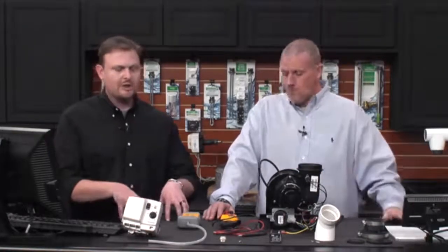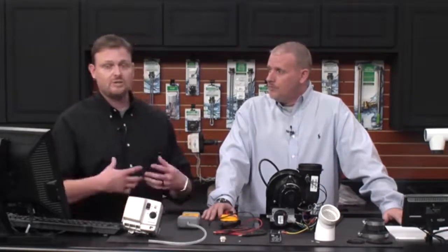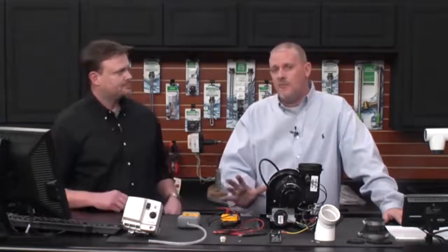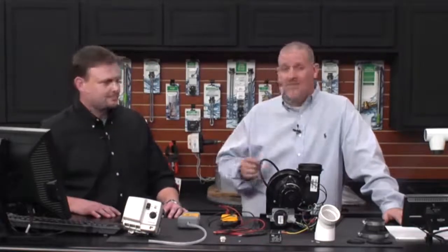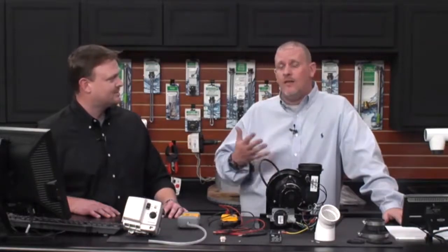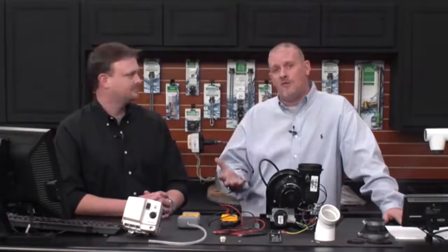We saw the flame for 4 seconds. We had 4 seconds to see it. We saw the flame, it starts running, starts heating up, and then we lost it. There's a couple of reasons that could possibly cause this, but I would say probably 90, maybe even 95% of the time, it's a dirty flame sense rod. That buildup that we were talking about earlier starts to build up on the flame sense rod itself, creates a dielectric barrier. The flame is actually present, and we just can't see it because that dielectric barrier is interrupting that signal, and it drops out on flame.